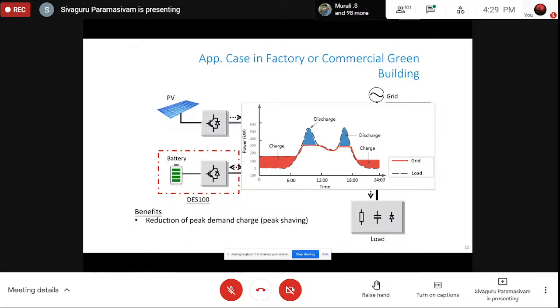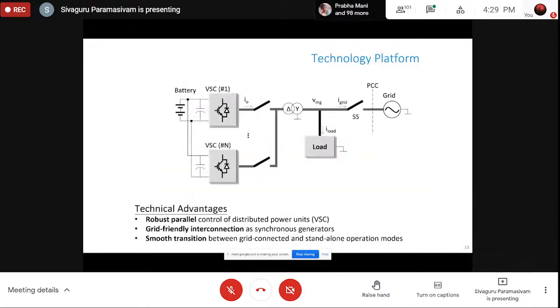In this system, the benefit is you don't have to upgrade your transmission system. Just say you have a 500 kilowatt load, as per this graph, for a very short period of time in a day. We don't want to increase the substations, the transformers, the transmission lines to 500 kilowatt, right? We can have everything designed for 300 kilowatt, and we can use the battery to compensate for that excess need in the load. And here you can see again power electronics has a major role.